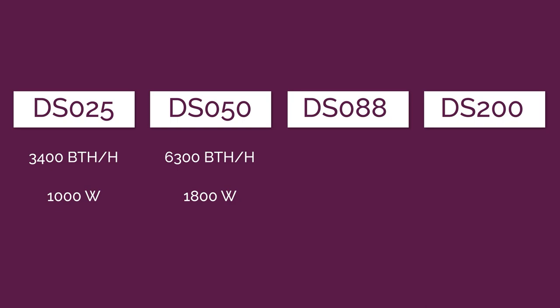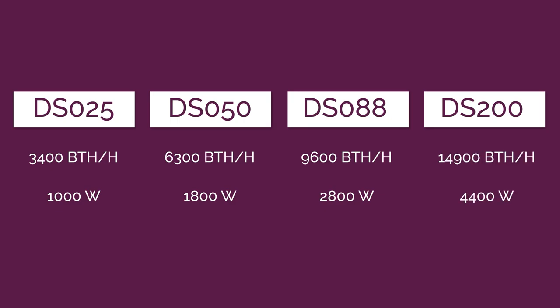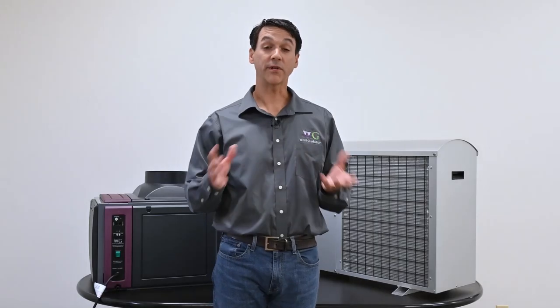Wine Guardian ducted split systems have four different capacity sizes. The first is a DS025, that's a 3,400 BTU unit at 1,000 watts. Our second size is a DS050, that's 6,300 BTUs at 1,800 watts. The third size is a DS088, that's 9,600 BTUs at 2,800 watts. And our last size is a DS200, that's 14,900 BTUs at 4,400 watts.